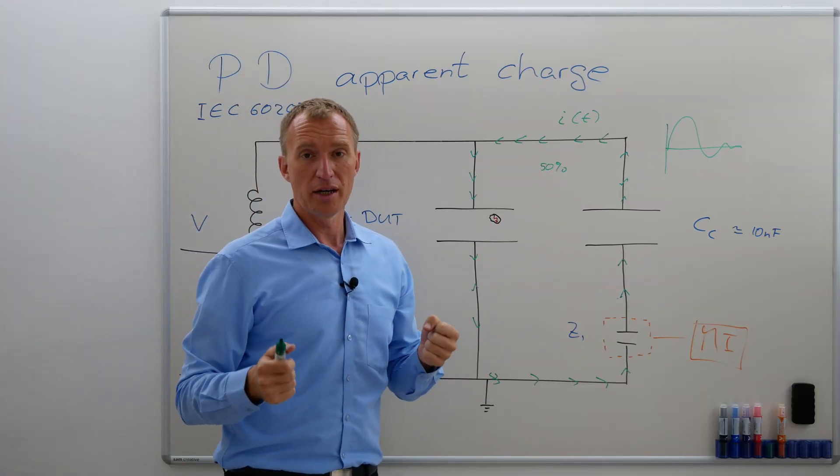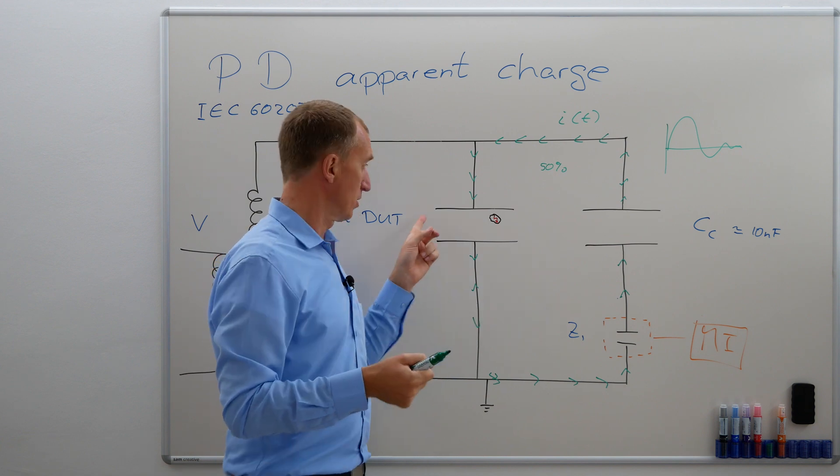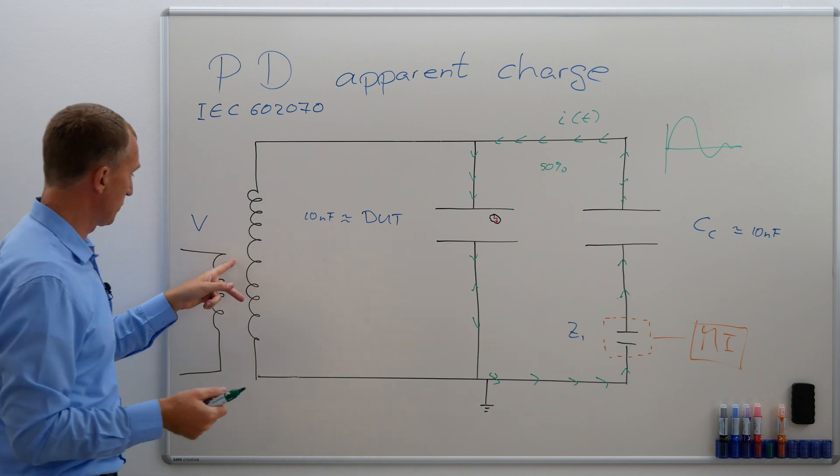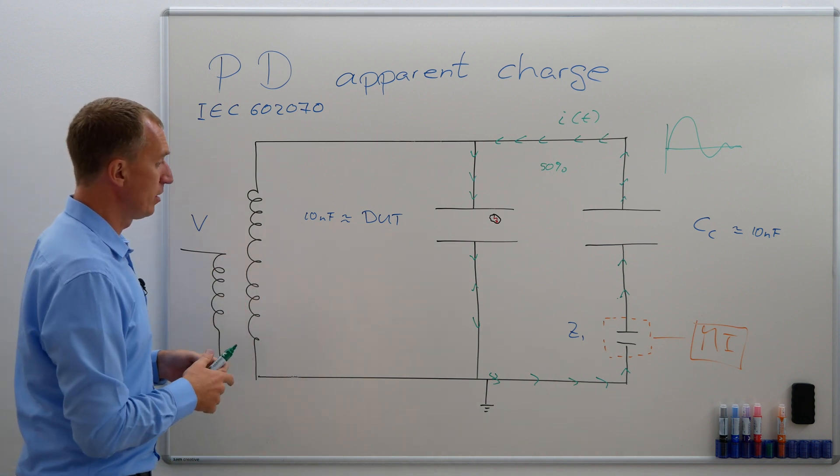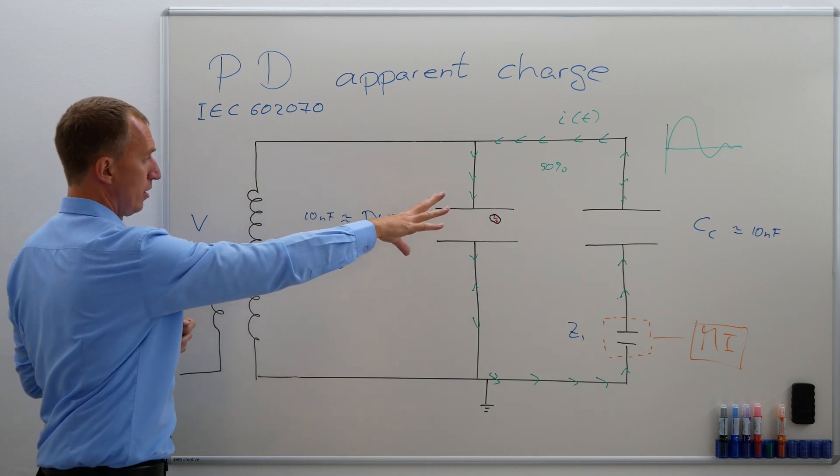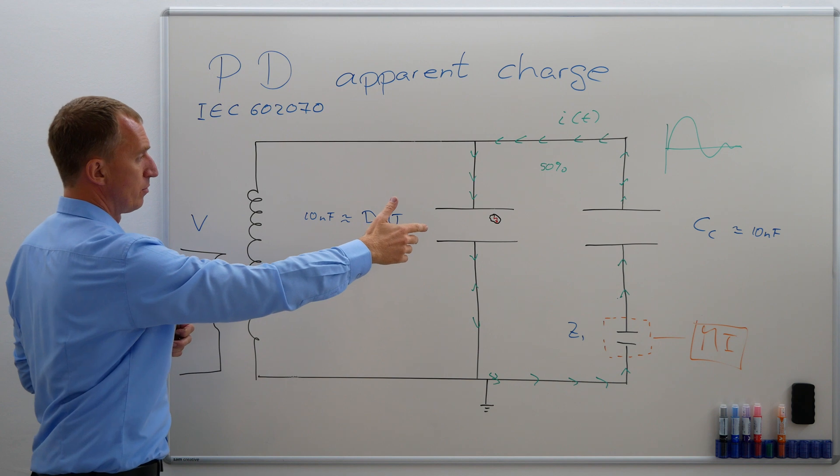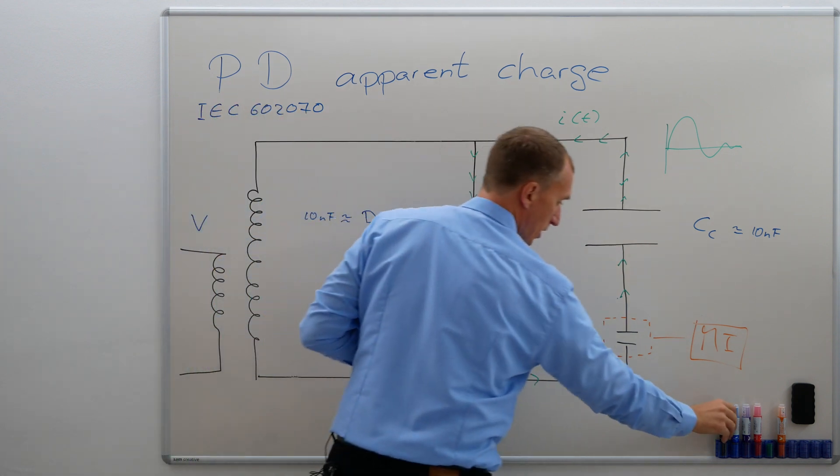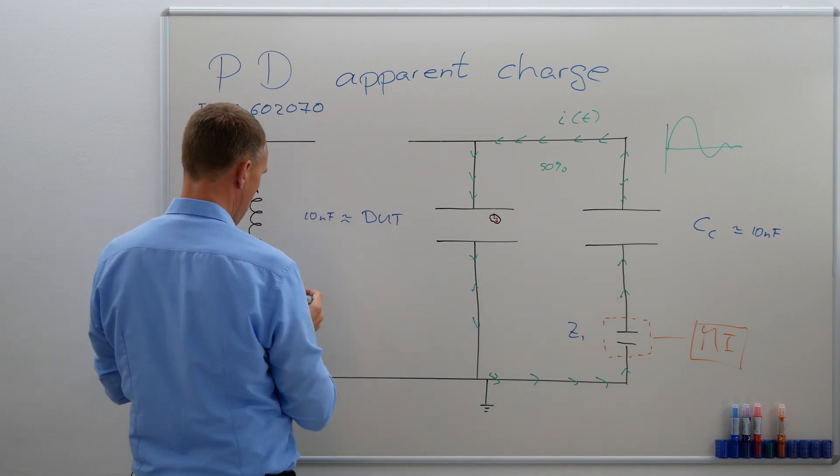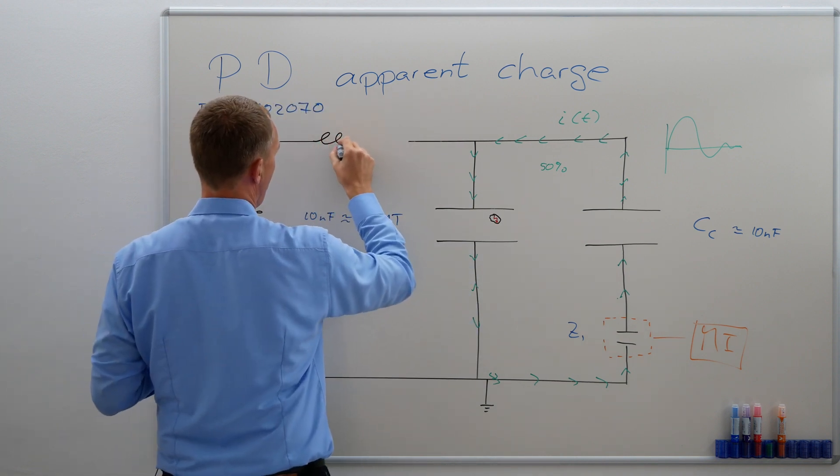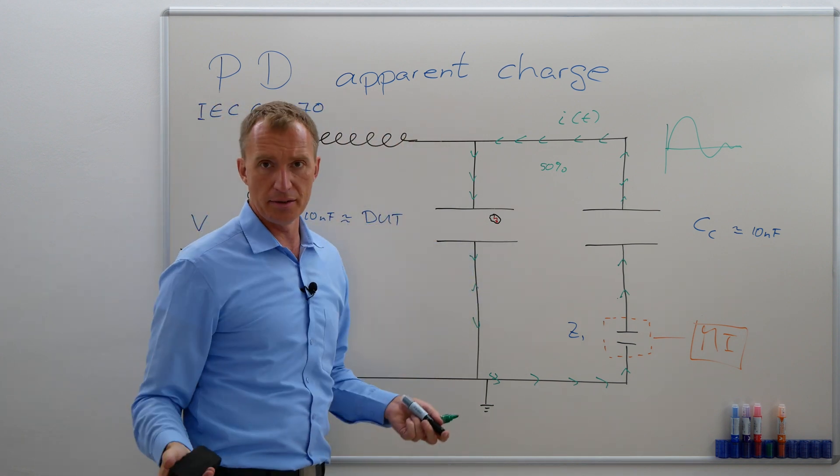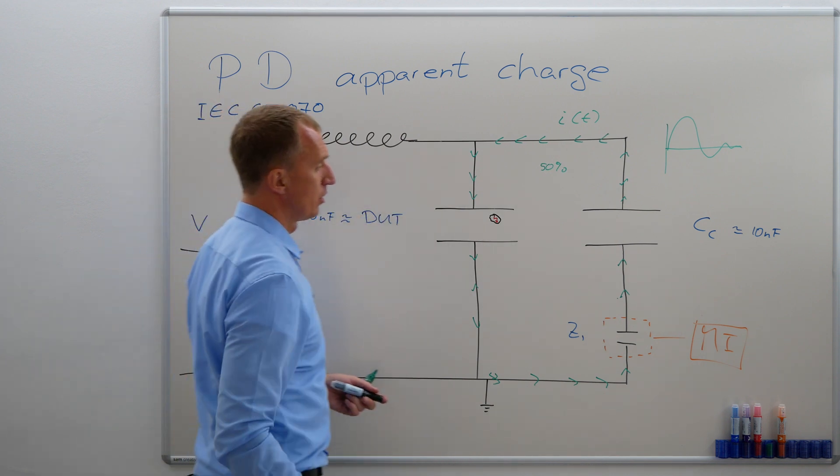This however is only true if there is nobody else helping us to recharge. And as we know, a high-voltage transformer usually has a lot of capacitance as well. So therefore, we have to try to limit the charge transfer going in here, at least for the time being, by means of, for example, a blocking impedance. And that is the reason why the IEC 60270 states that there needs to be a blocking impedance in here, in order to at least hinder the charge transfer coming from here to here.